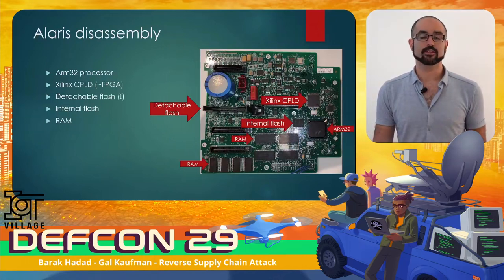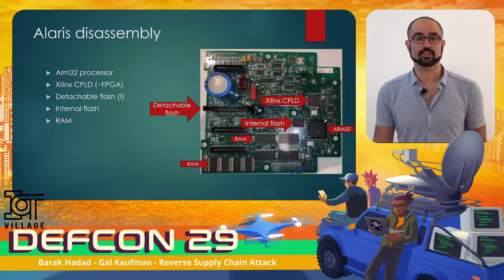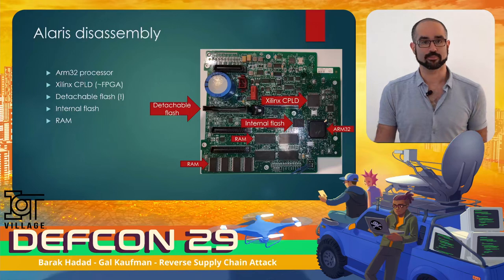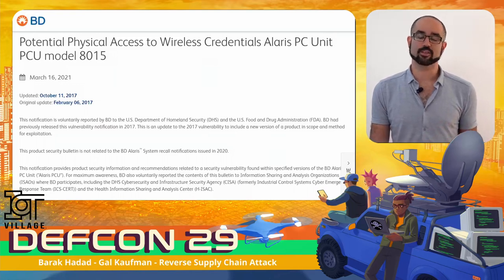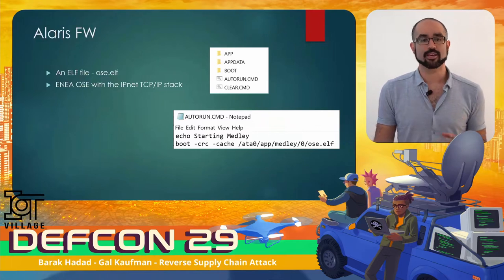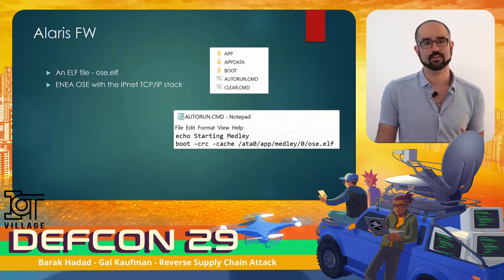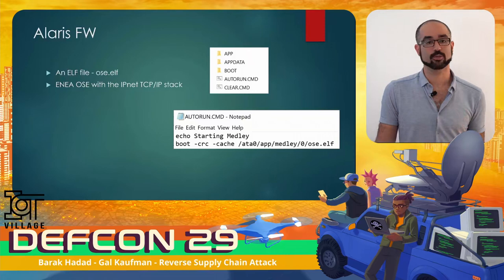We took the device apart and examined the main board. We identified a 32-bit ARM processor, a Xilinx CPLD — we actually have no idea why they need that in an infusion pump — and a detachable external flash card containing the firmware, along with an internal flash and some RAM. We found a vulnerability on BD Alaris's website stating that physical access may lead to wireless credentials and maybe some other confidential data. Mounting the flash card, it contains an autorun script pointing to an ELF file named OSE.ELF. The device runs the ENEA OSE operating system and the IPNET TCP/IP stack, vulnerable to a set of vulnerabilities Armis published two years ago named Urgent 11 — still relevant today.